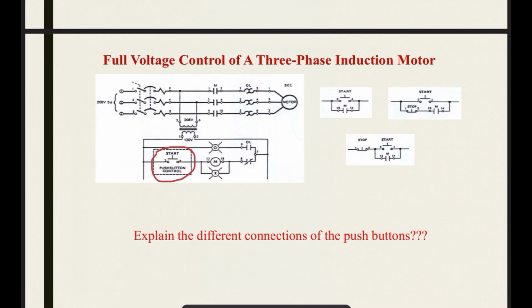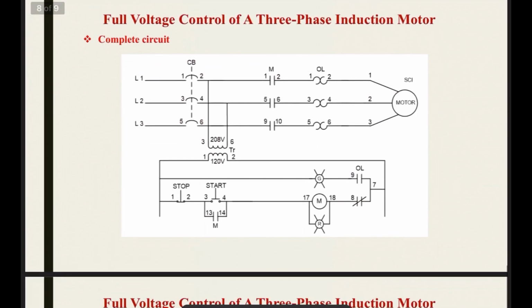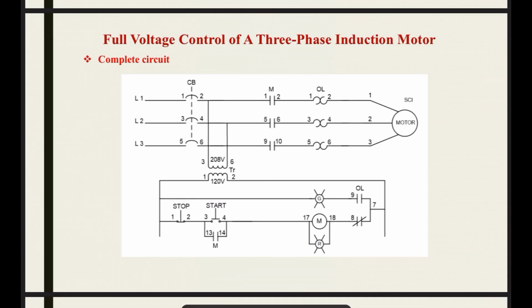Okay, this is the explanation of the three possible connections of the start and stop push buttons. Now let's explain the operation of the full voltage control. This is the complete circuit of the full voltage control of the three-phase induction motor. In case we need to start the motor, this is the squirrel cage motor. So the steps: number 1, close the circuit breaker CB.